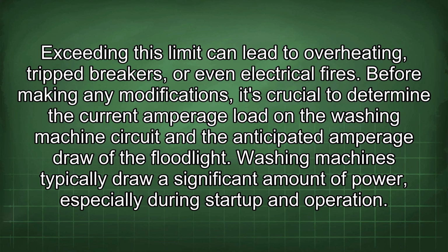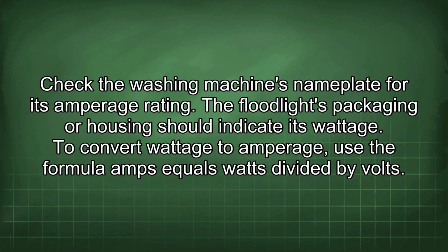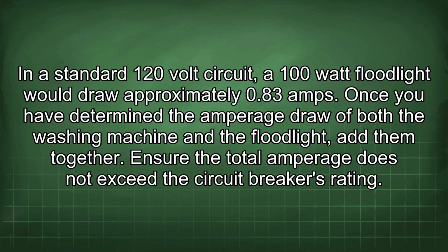Before making any modifications, it's crucial to determine the current amperage load on the washing machine circuit and the anticipated amperage draw of the floodlight. Washing machines typically draw a significant amount of power, especially during startup and operation. Check the washing machine's nameplate for its amperage rating. The floodlight's packaging or housing should indicate its wattage. To convert wattage to amperage, use the formula amps equals watts divided by volts. In a standard 120-volt circuit, a 100-watt floodlight would draw approximately 0.83 amps.